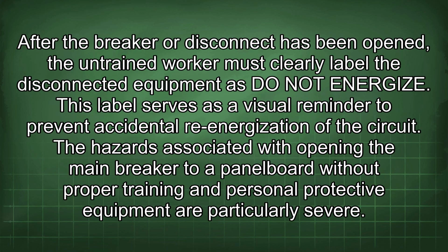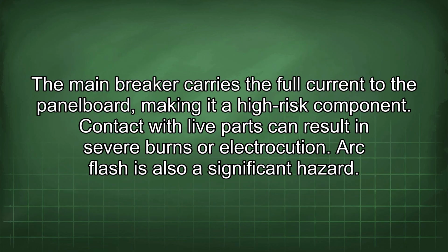After the breaker or disconnect has been opened, the untrained worker must clearly label the disconnected equipment as "Do not energize." This label serves as a visual reminder to prevent accidental re-energization of the circuit. The hazards associated with opening the main breaker to a panel board without proper training and personal protective equipment are particularly severe. The main breaker carries the full current to the panel board, making it a high-risk component. Contact with live parts can result in severe burns or electrocution.